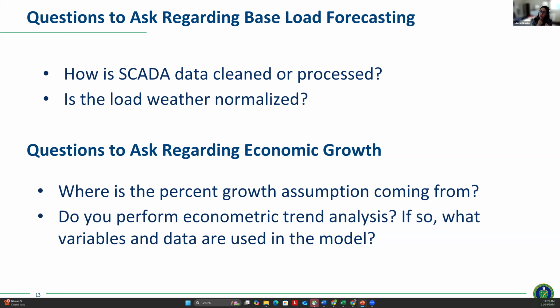It's also important to understand where the economic growth assumption is coming from. It's typically an annual percentage growth applied to a substation or feeder to extrapolate that out. Is that based on trend analysis using demographics and local economic indicators, or is it a default left to the local area planner to choose? These are important questions to ask.